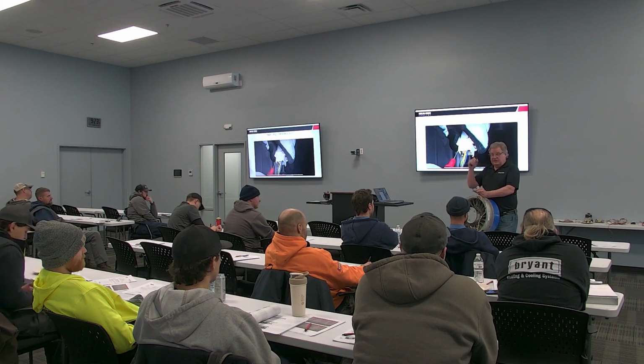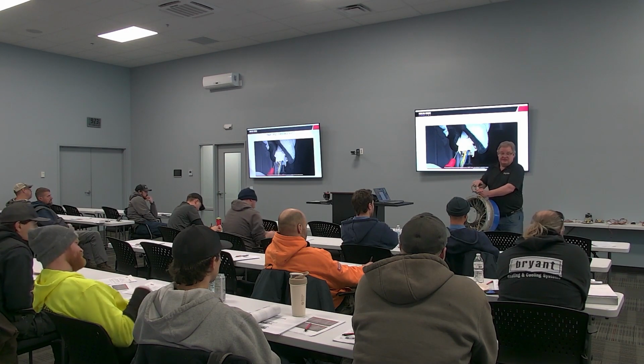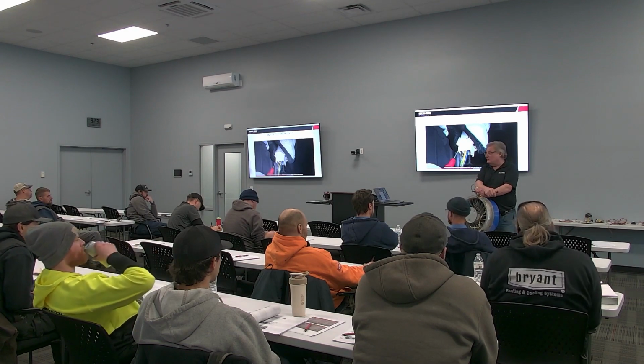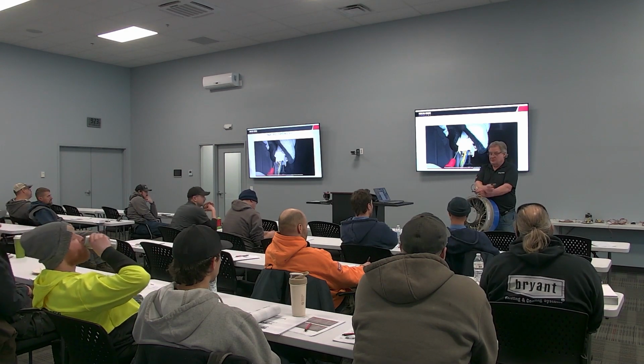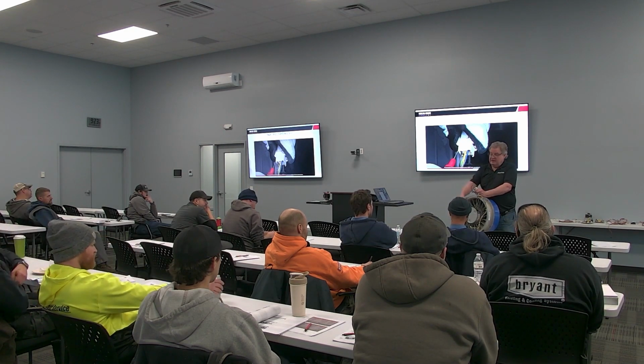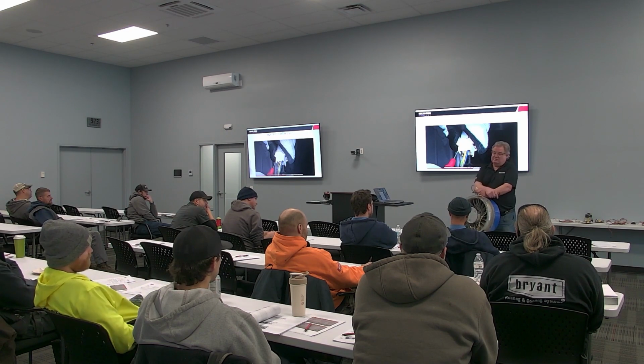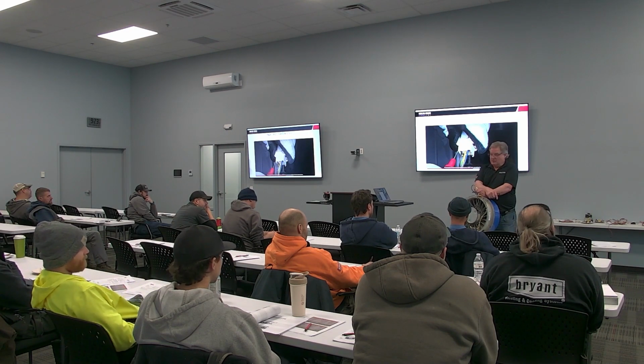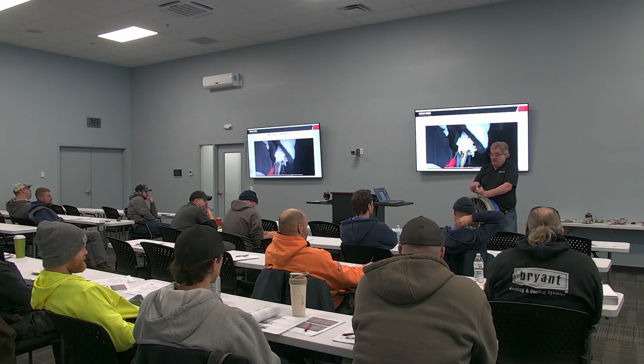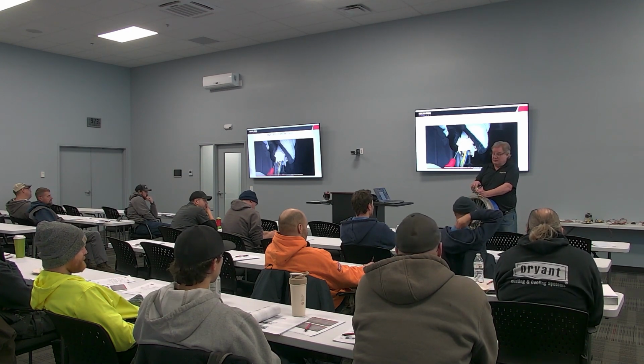So remember, reset power, wait 3 minutes, turn it back on, check it again. If I still don't have 10 volts DC, guess what's wrong? The motor's bad. The rectifier inside the motor is bad, so we're no longer creating DC volts to turn it on. This is fried. Okay, I do have 10 volts to the orange.